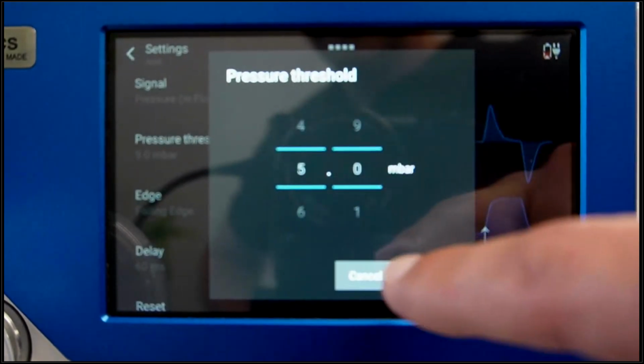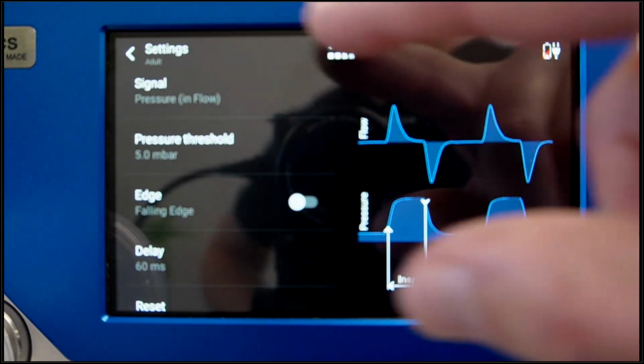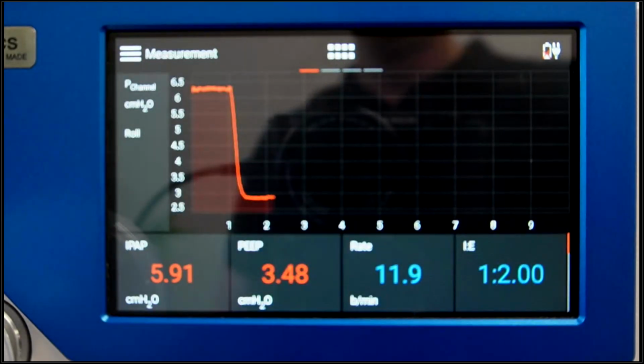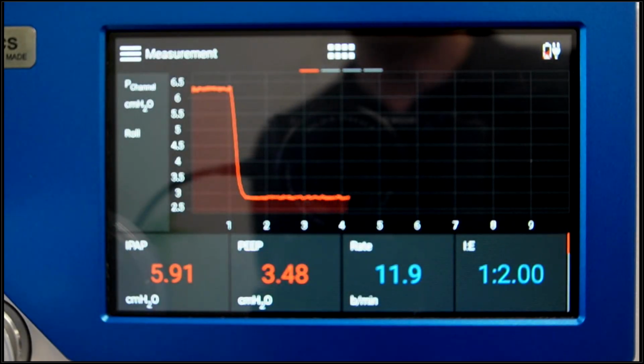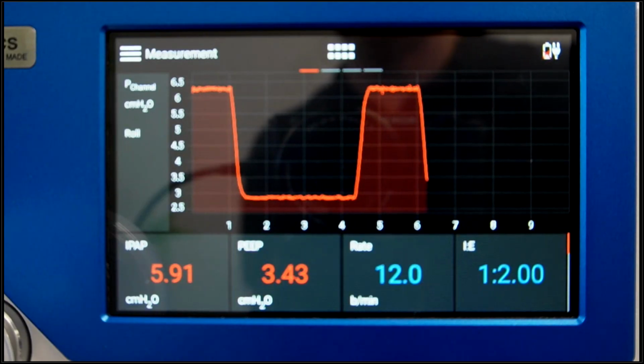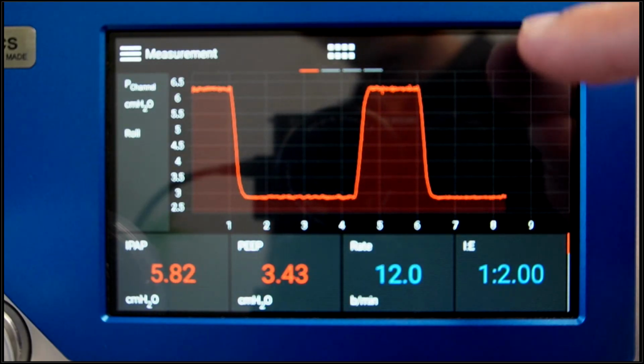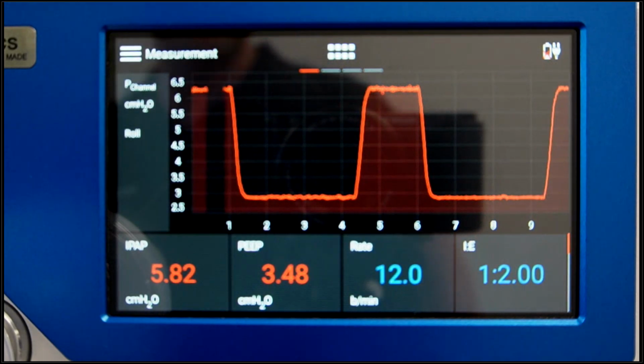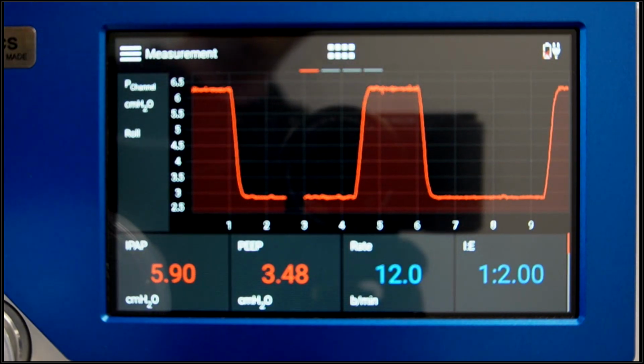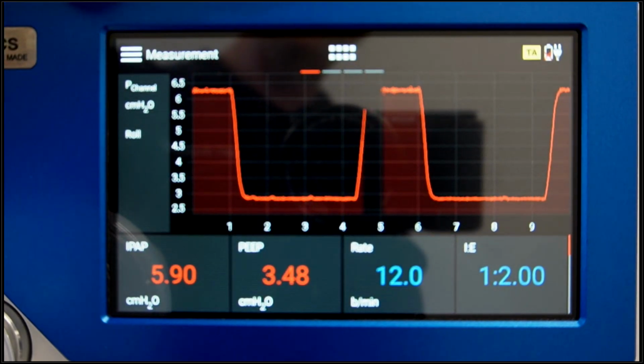I'm going to set it to 5 millibar or centimeters of water on a falling edge. So as soon as I have applied these settings, now I can see that my gas flow analyzer is able to measure my breath-based parameter. And you can see there is a T flashing up in the right corner of the screen when a trigger is being detected.